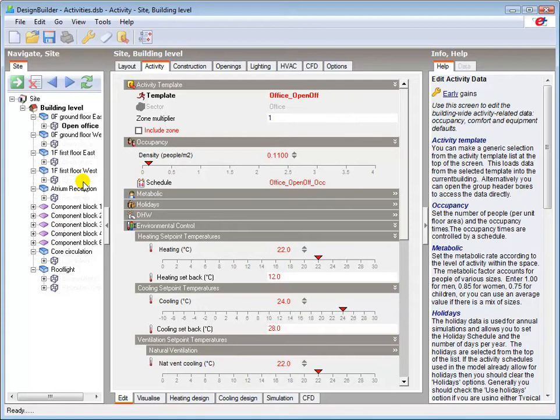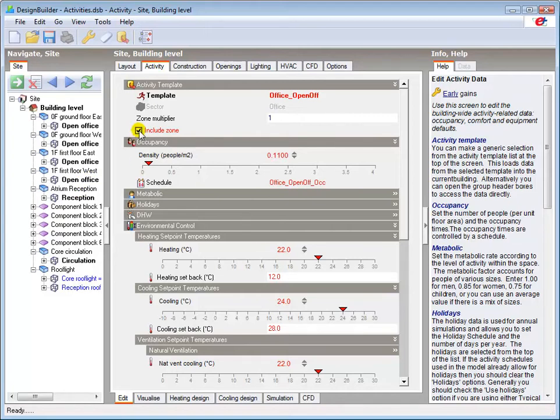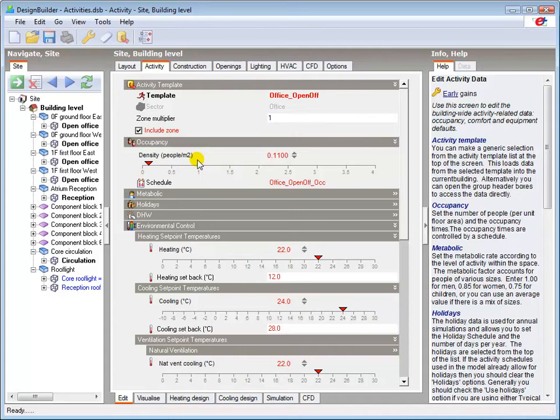The activity template loads default data in the model relevant to the activity type. For example, the occupancy density here for an open plan office will be higher than that of a cellular office, and the heating set point will be higher than the default for say a store.